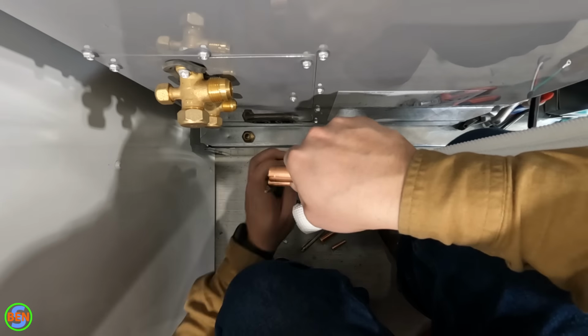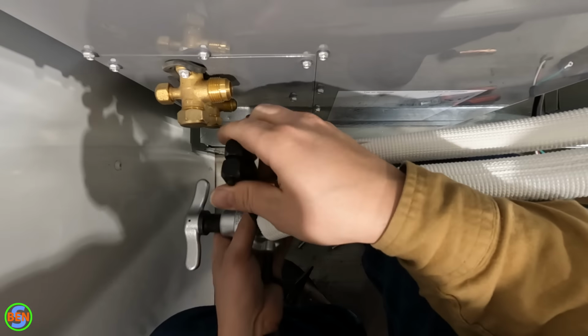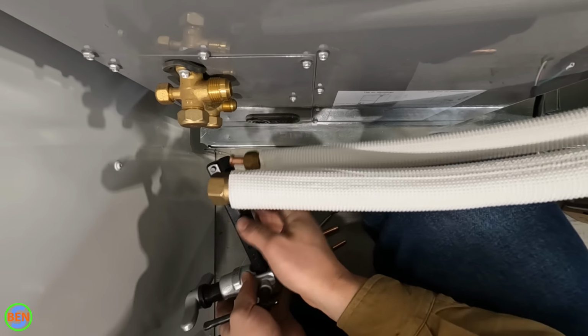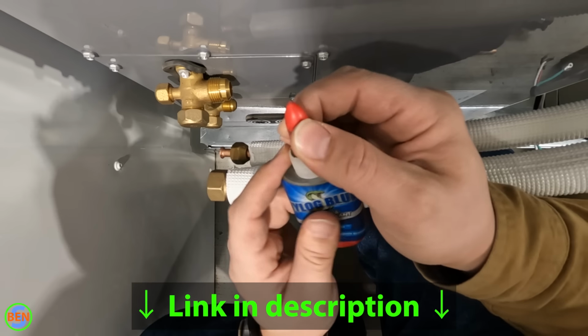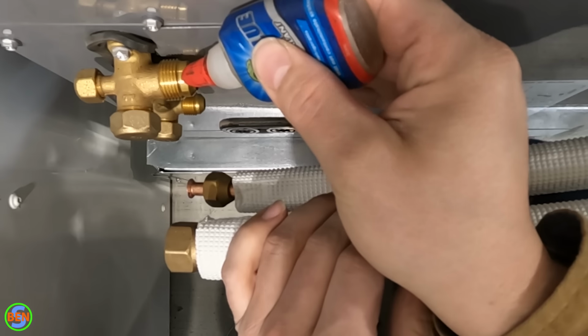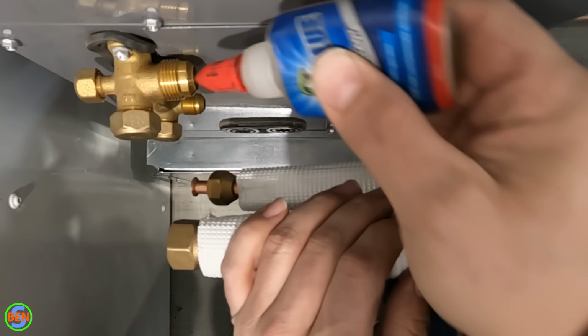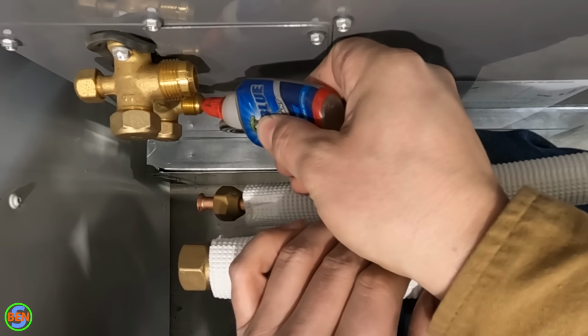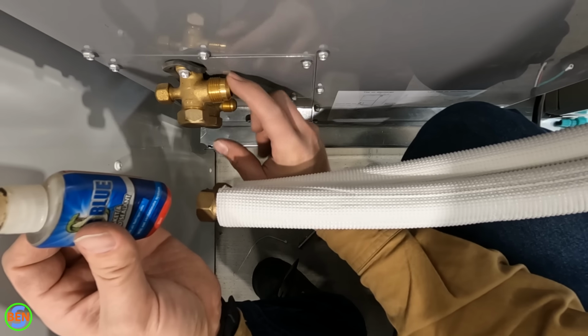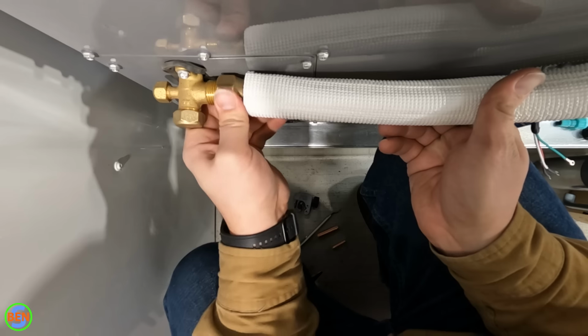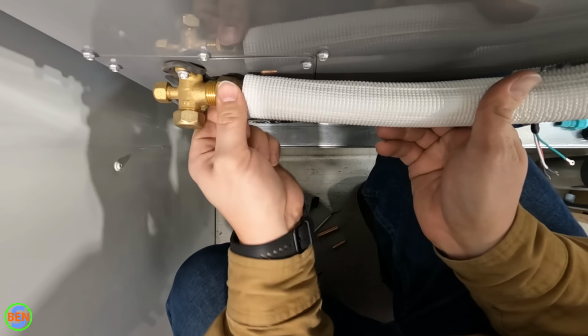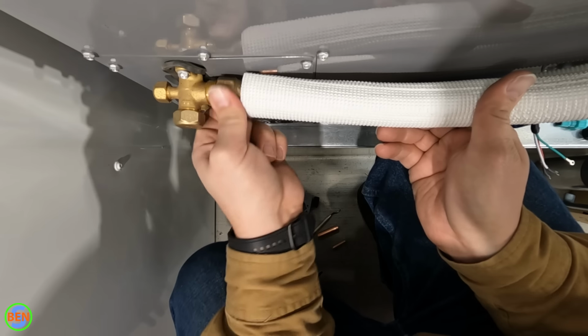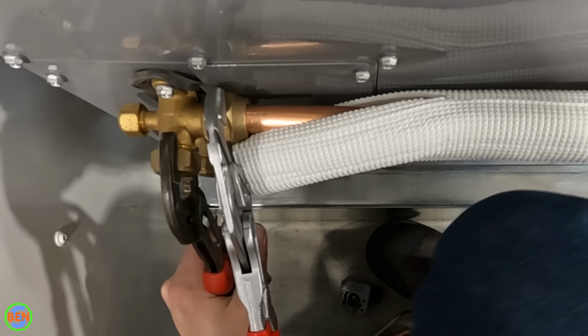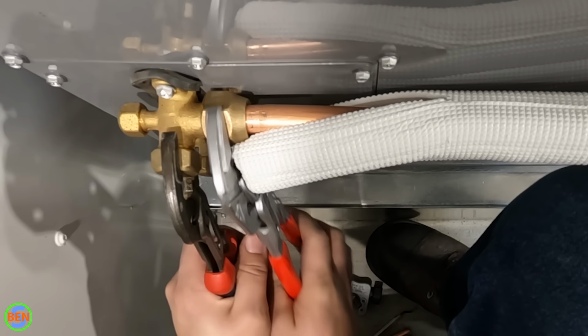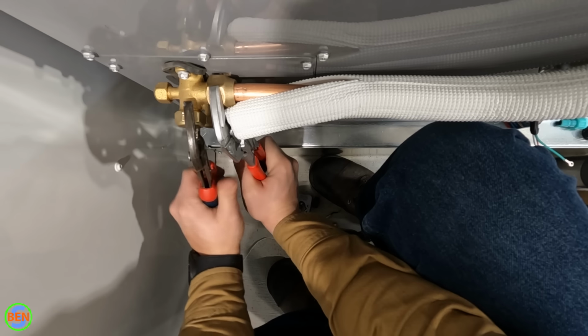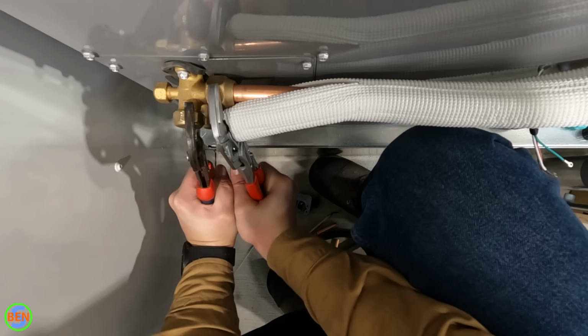Now when you make a connection to the actual unit or any of the flare connections that you're making, you'll want to use a little bit of Nylog Blue. Now this stuff is compatible with R410A oils, and that's what's important, and you're just going to use a tiny little bit of it. It's almost like the consistency of honey, and the benefit to this is that it makes your fitting go together a little bit smoother. There's going to be less binding between the copper and the brass as you connect it, and it just does a really good job of making sure that you get a leak-free connection. It's not so much of a sealant, but rather more of a lubricant, and it's a really useful product.